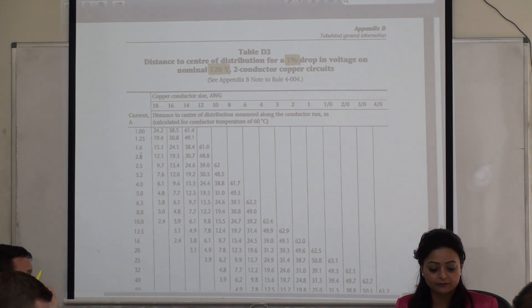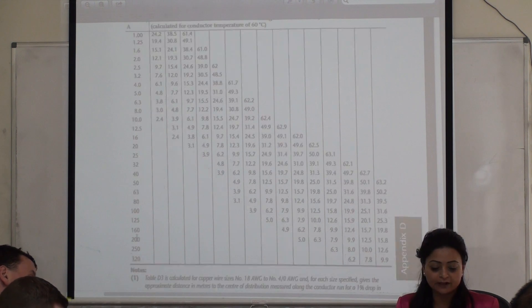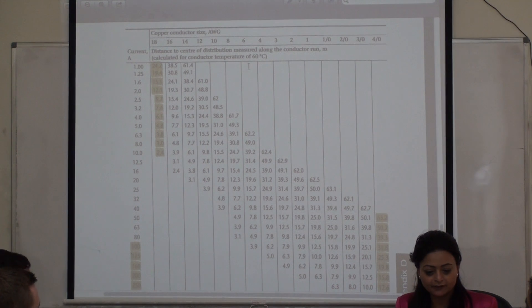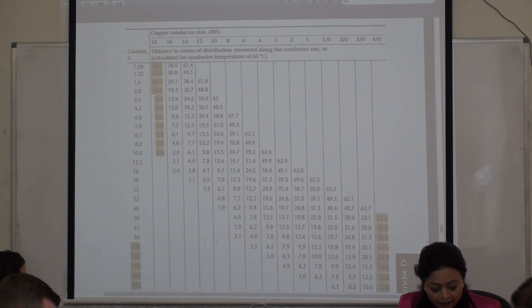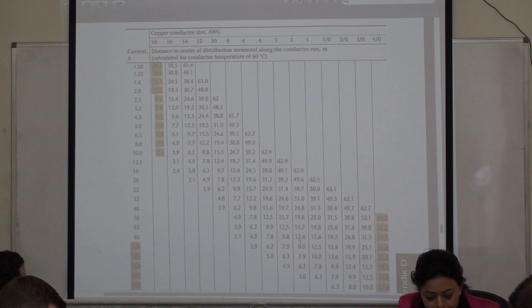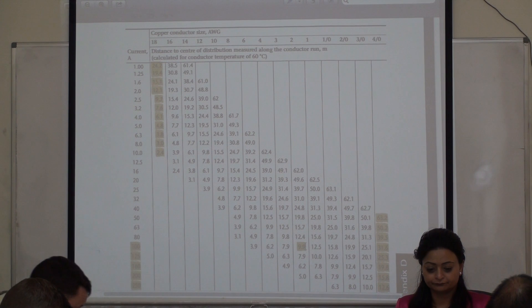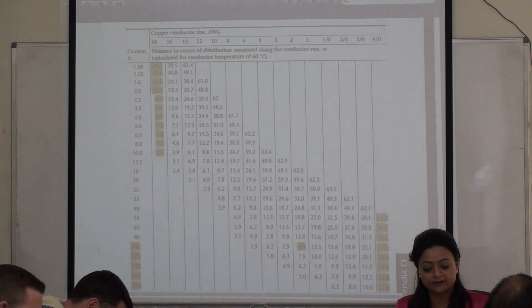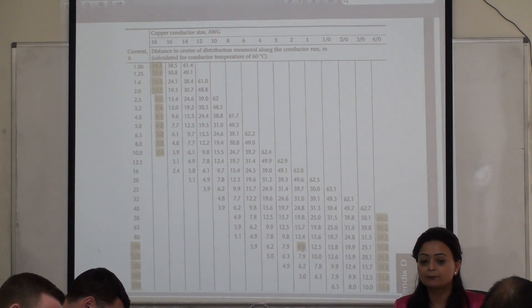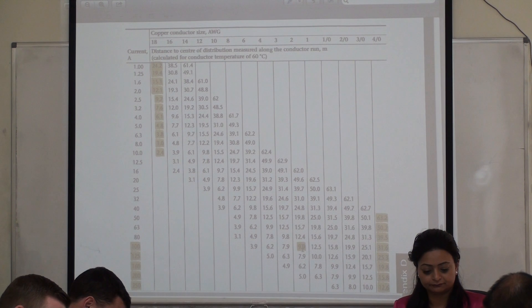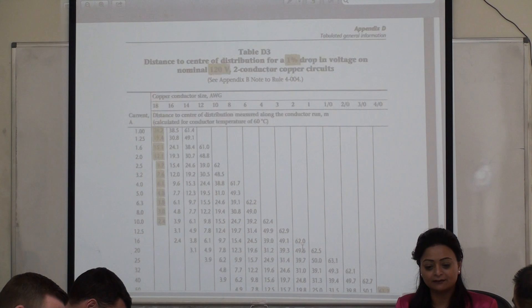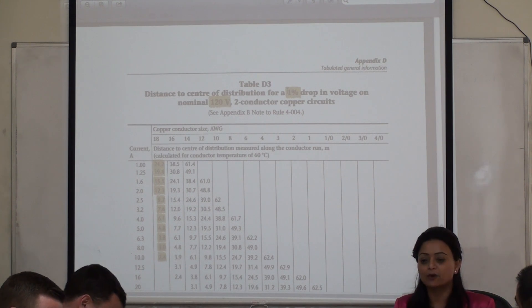Based on 1% drop and 120 volts — let's say the load was 100 amps and I'm using Number 2 wire — for Number 2 at 100 amps, 1% drop, 120 volts, I can go up to 9.9 meters. Is that correct, guys? This is easy only when 120 volts and 1% applies.